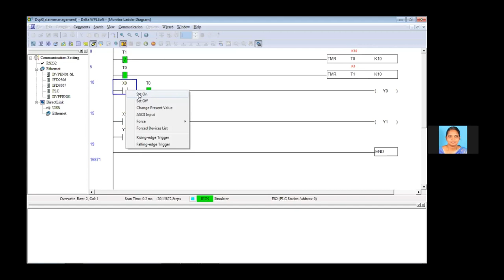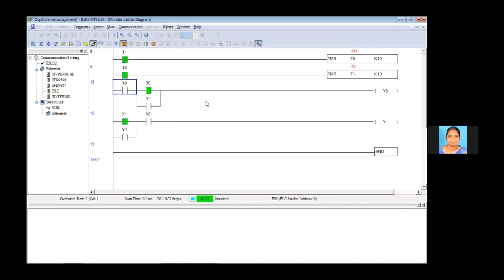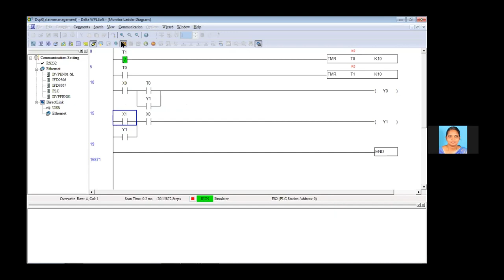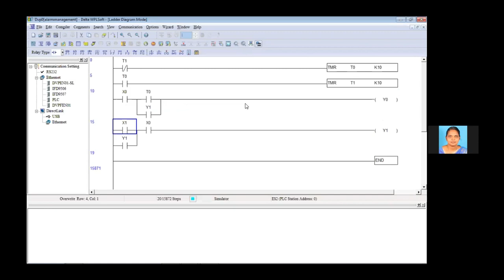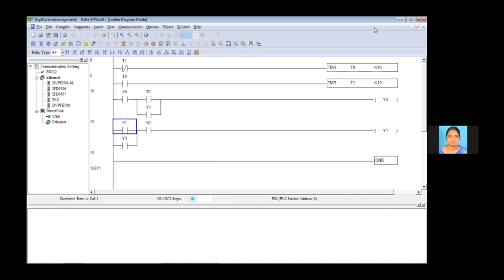Now the plant is working in the normal condition. The timers T0 and T1 are also continuously running to check for the next alarm condition. Whenever the pressure increases beyond 60 psi again, the pressure sensor X0 will sense it and put it to the on state, putting my LED in the blinking state. Again, the operator will go there and take care of it to bring it to the normal condition. Until his maintenance work is over, both will be in the high state. Once his maintenance work is over, both will go to the off state. So like this, the timer can be used. It's just one example where a timer can be used for alarm management in some industrial applications.